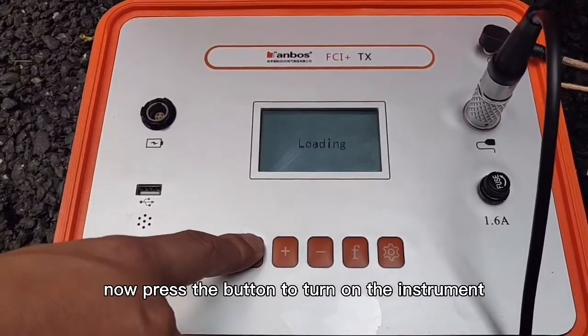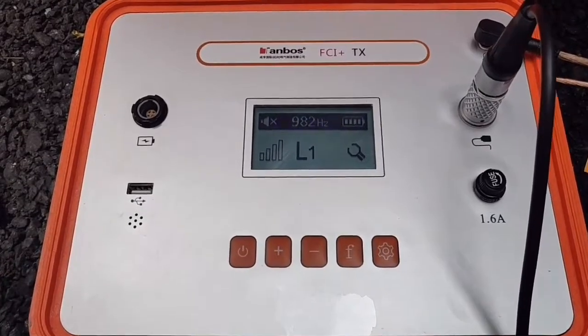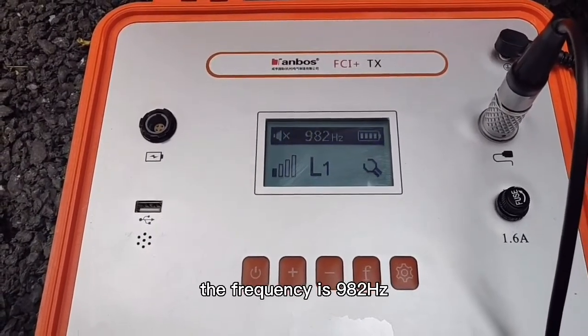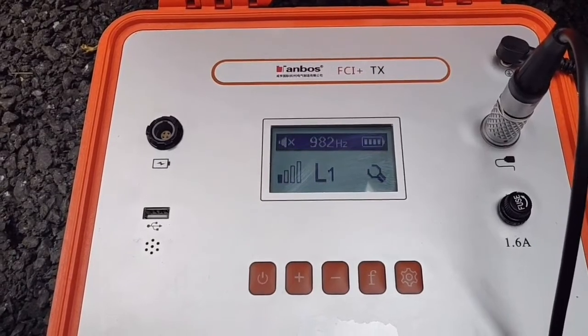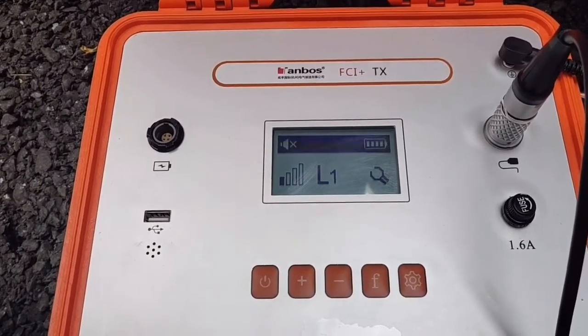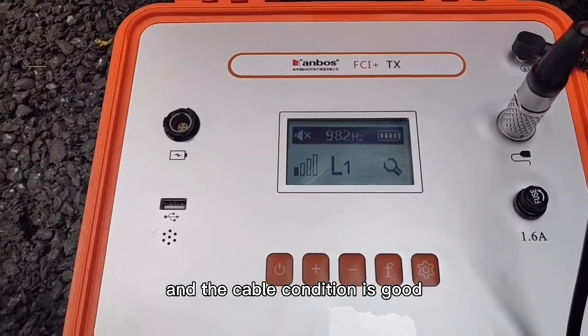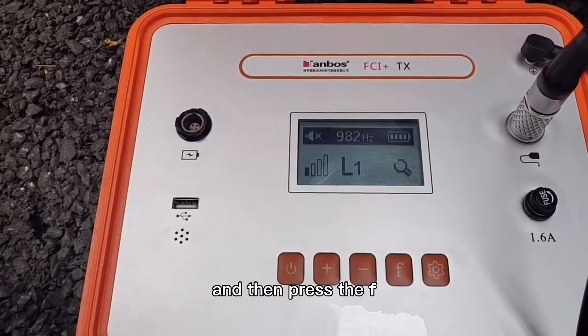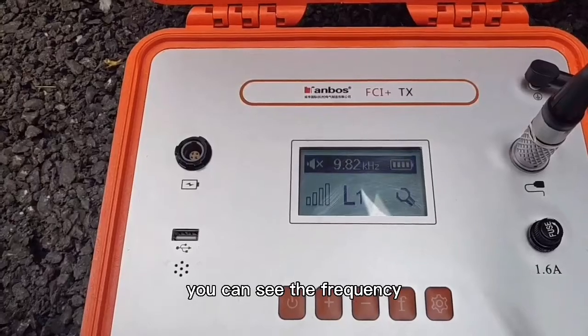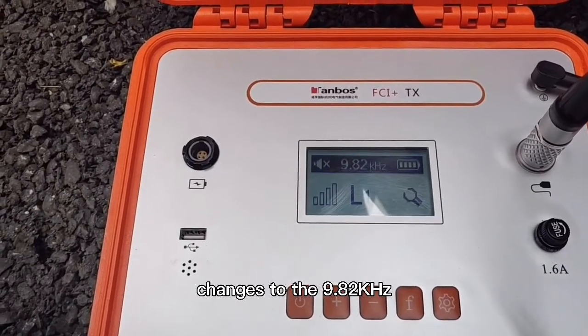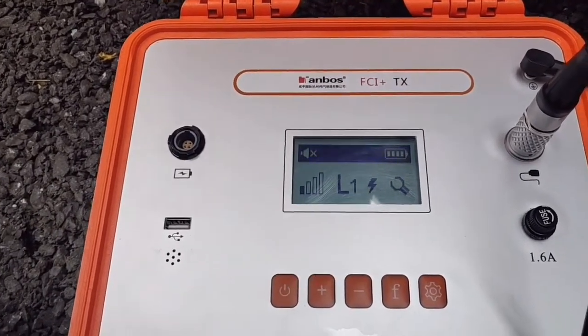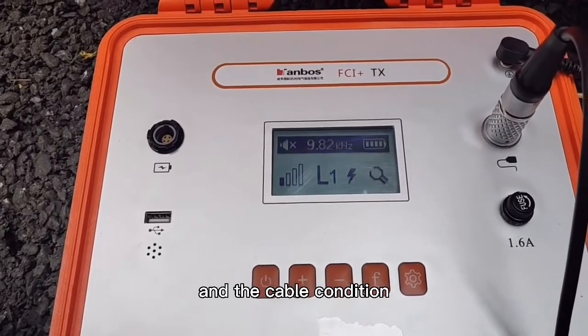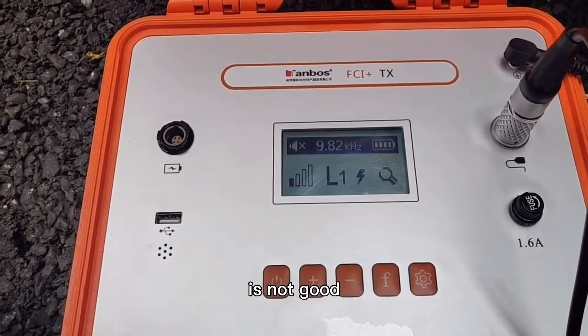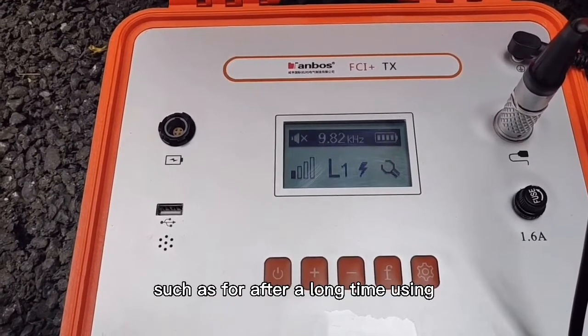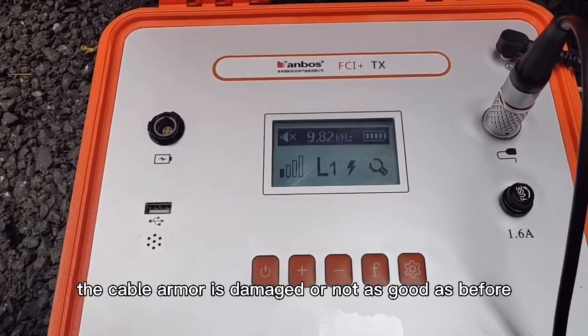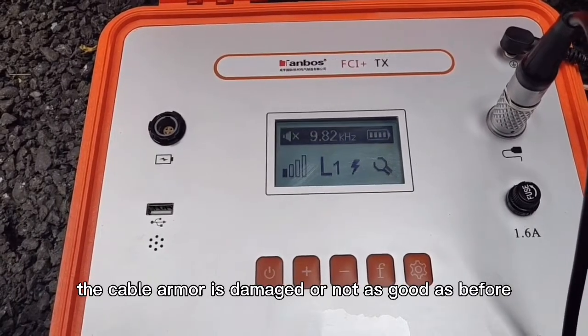Long press the button to turn on the instrument. Now we can see the frequency is 982 Hz. It is suitable for the long cable and the cable condition is good. And then press the F. You can see the frequency changes to the 9.82 kHz. It is suitable for short cable and the cable condition is not good, such as after a long time using, the cable armor is damaged or not as good as before.